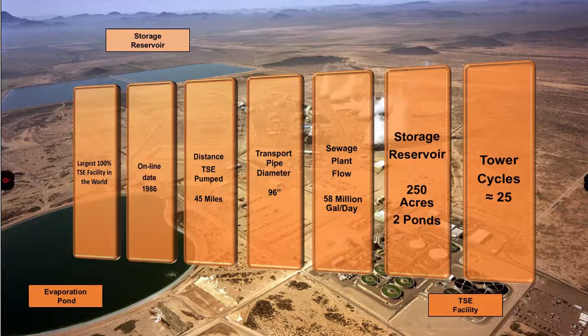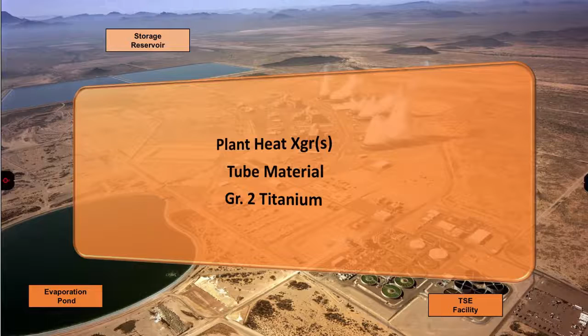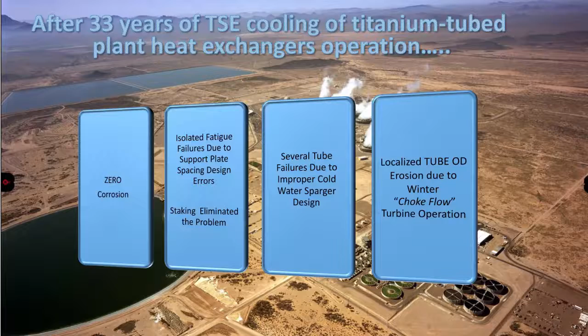All of the plant heat exchangers at this facility, in this case study, are CP grade 2 titanium. They've been there for 33 years with zero corrosion in any of the exchangers. The only damage has been occasional mechanical issues—some sparger design problems and choke flow conditions from low operating temperature, which washed the top of the titanium tube with high velocity steam, causing modest erosion. Other than that mechanical damage, there has been zero corrosion on that unit.